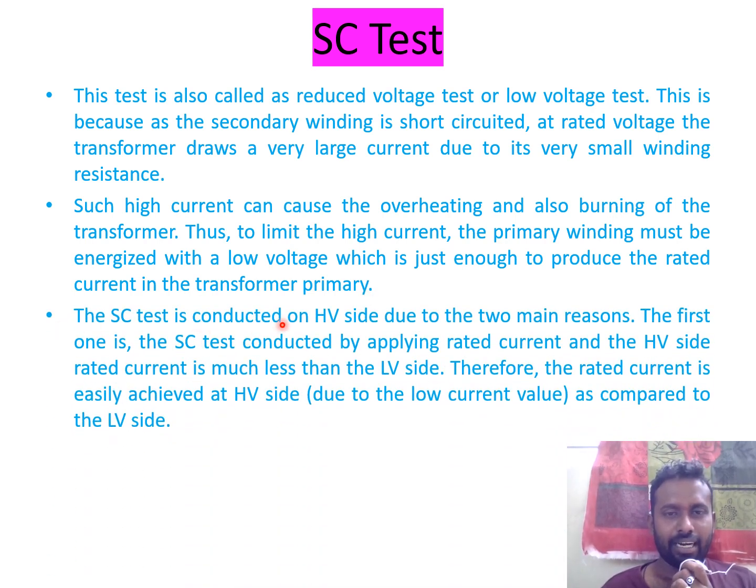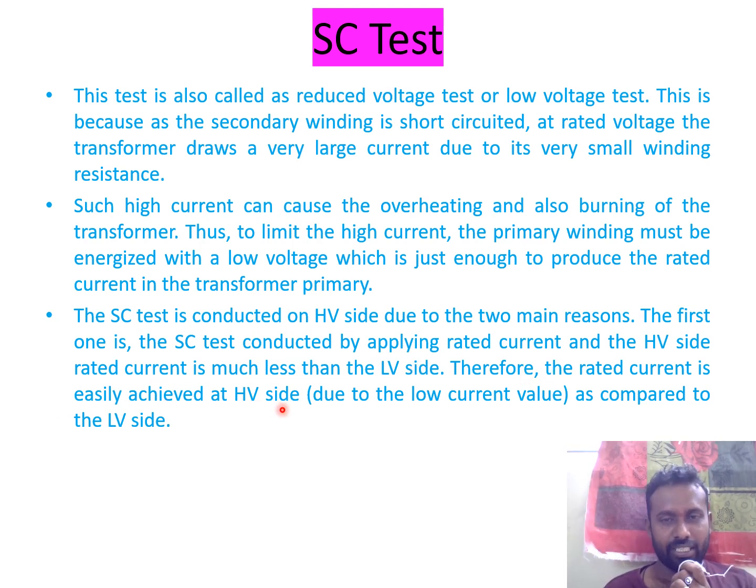This test is conducted on the HV side for two main reasons. The first one is that the short circuit test is conducted by applying rated current, and the HV side current is much less than the LV side current. Therefore, rated current is easily achieved on the HV side due to the low current value as compared to the LV side.